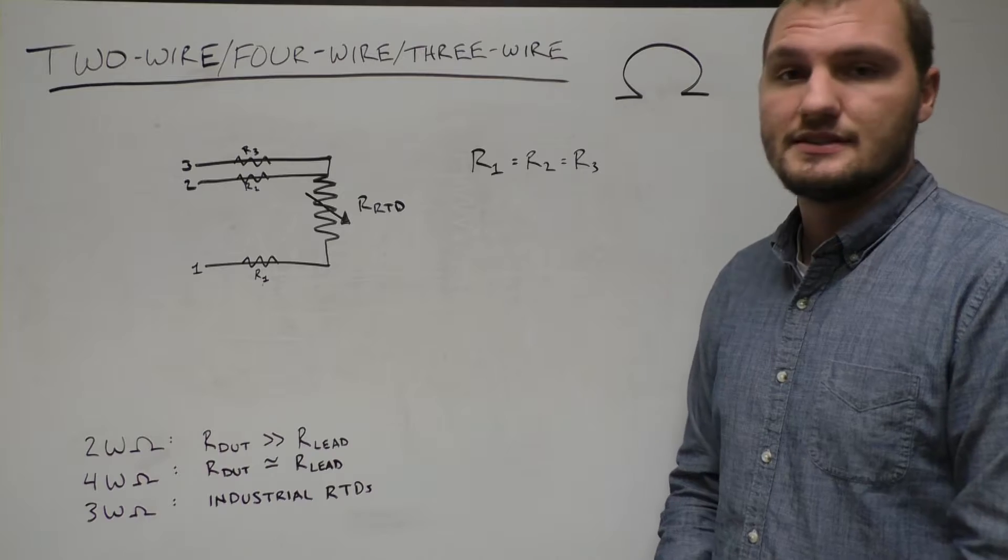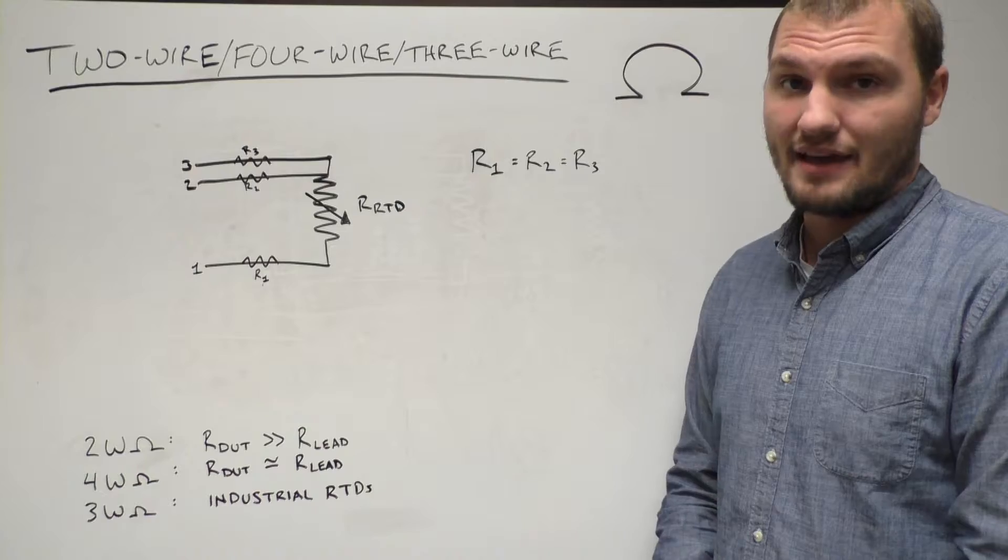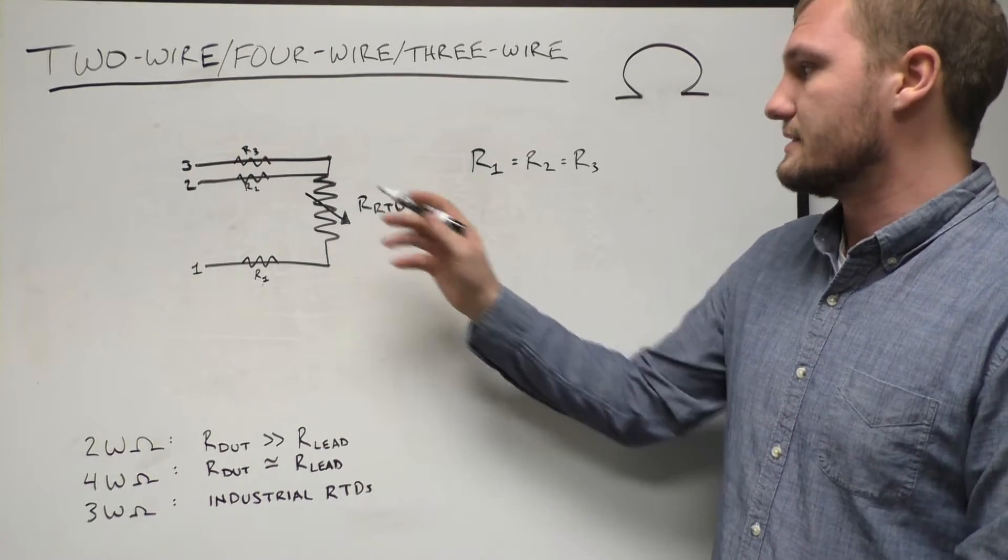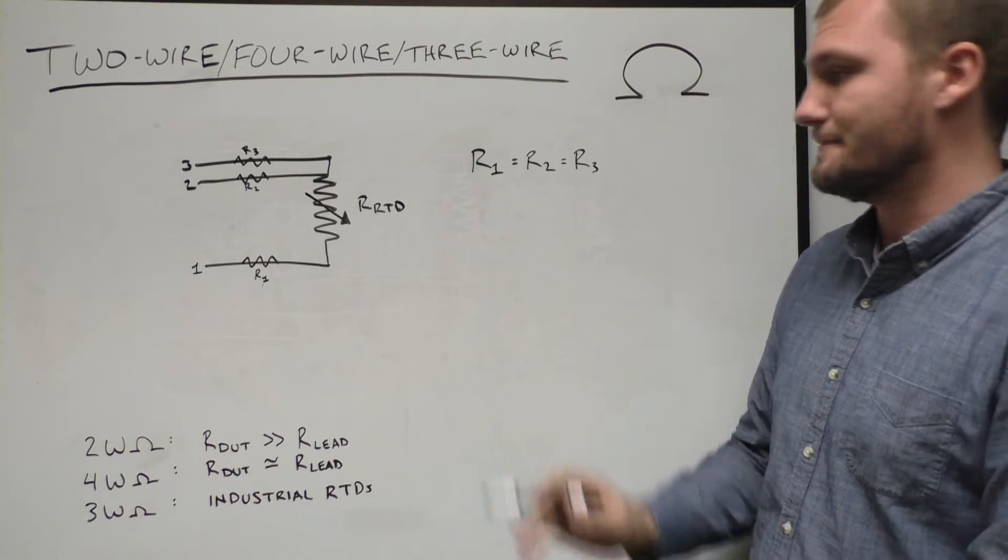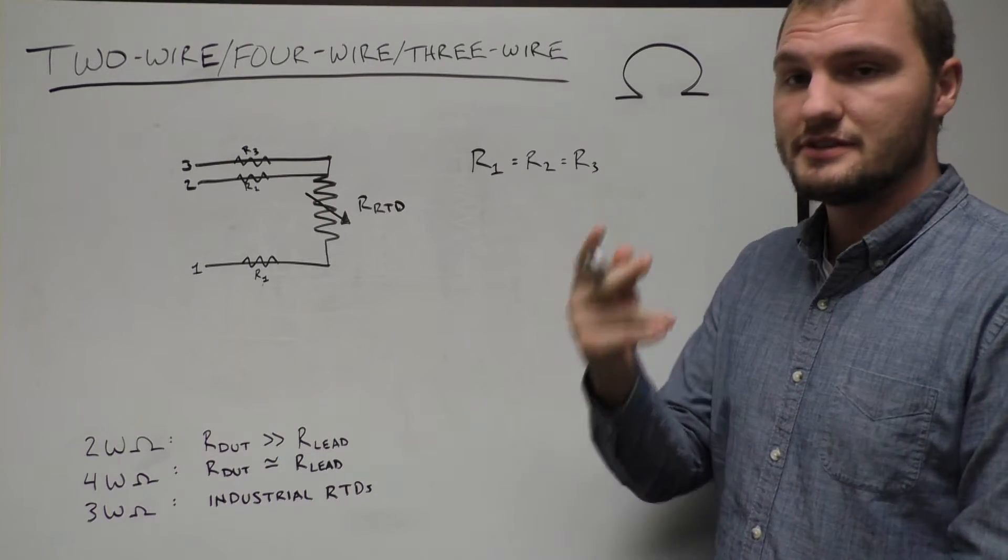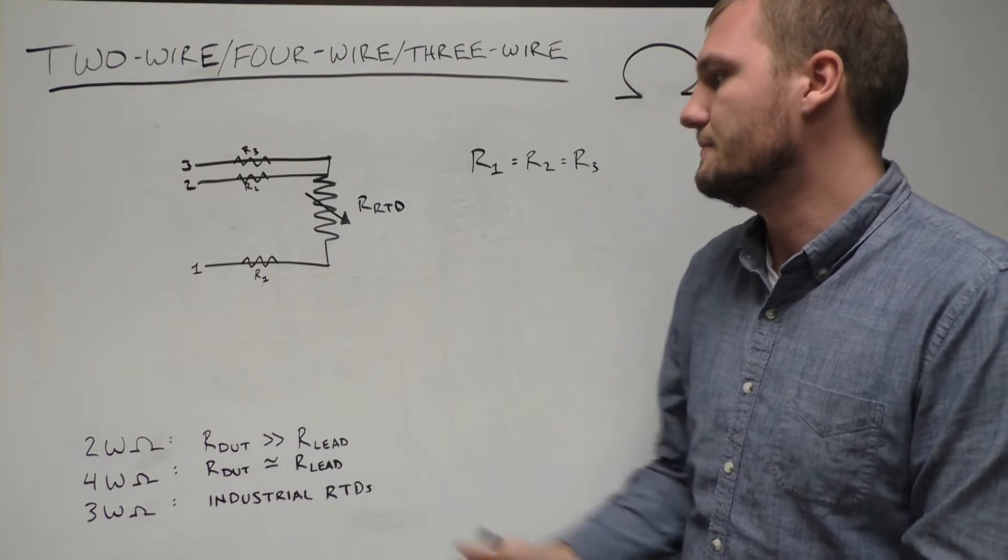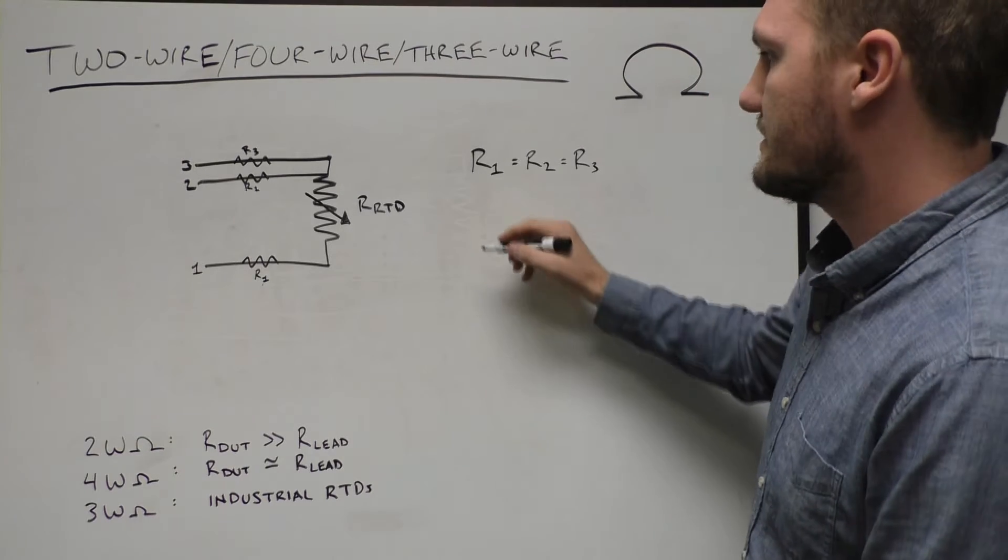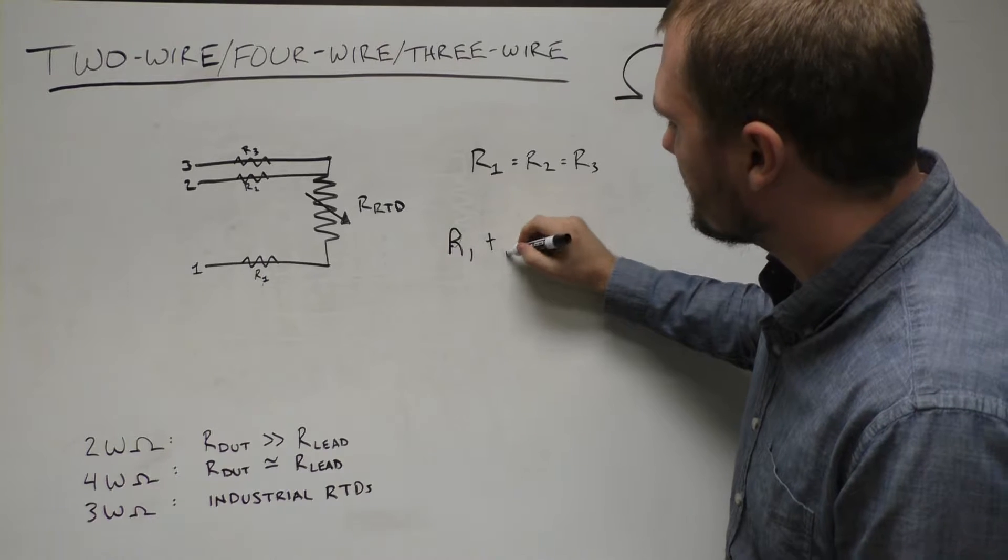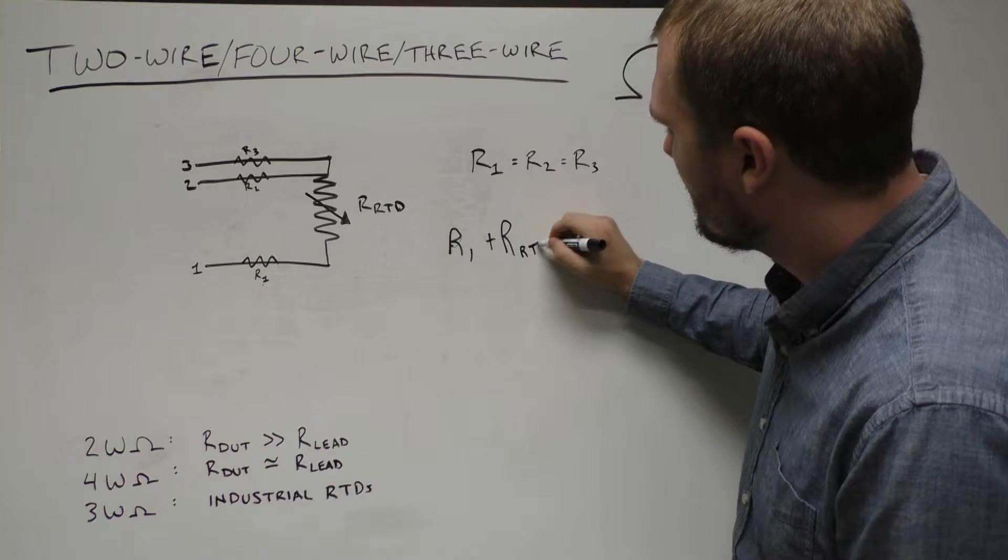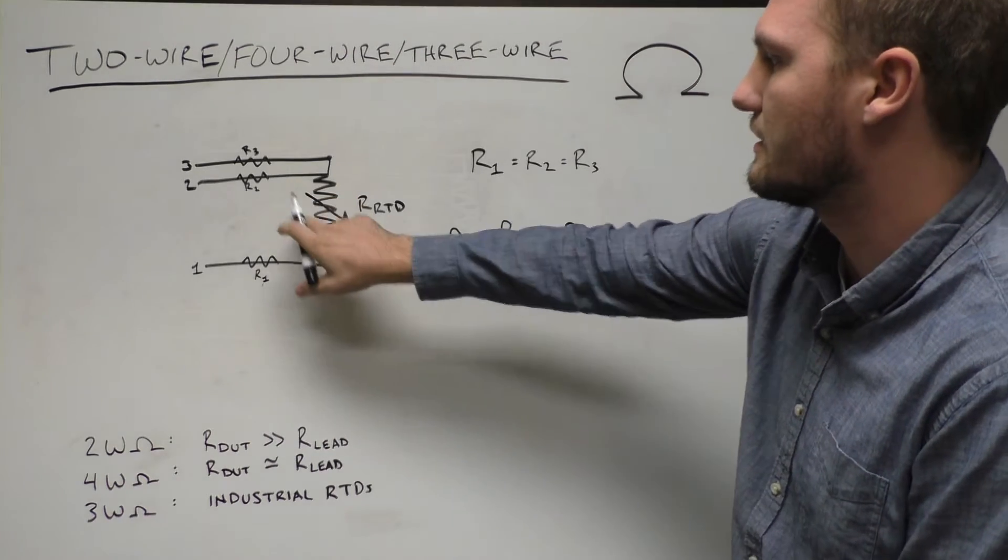The idea here is that rather than using the circuit to eliminate the lead resistance, we're going to use math. So, one of the caveats of 3-wire is that all three of the leads need to have the exact same resistance. And now what you do is you make two separate two-wire measurements. You make a two-wire measurement between points 1 and 2, which gives you the resistance of R1 and R of the RTD and R2.